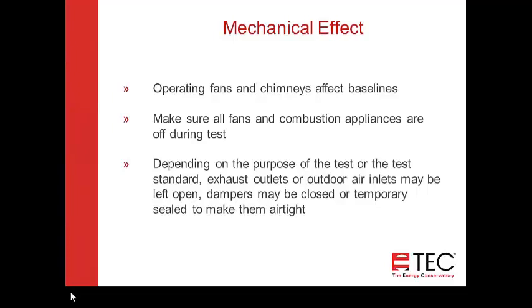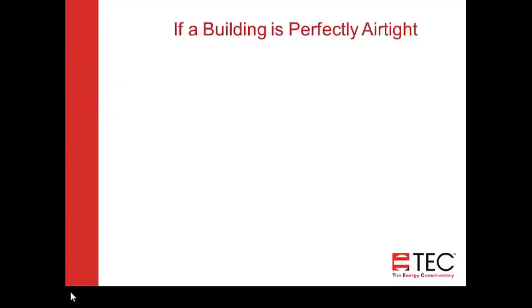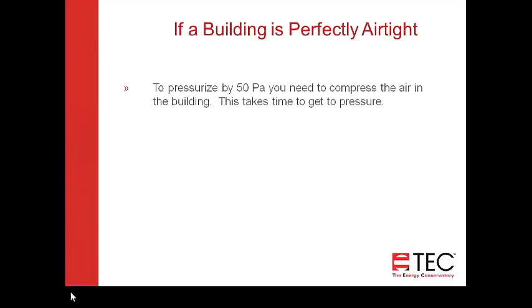Operating fans and chimneys will definitely affect your baseline and pressures in the building. You need to make sure all fans and combustion appliances are off during the test. This requires getting mechanical people out there who understand the building to make sure everything is turned off. Even when they think everything is off, you'll get on the roof and still find some exhaust package rooftop units running. One thing that's very different going from single-family residential to commercial buildings is the size of exhaust and outdoor air inlets — sometimes the size of an overhead garage door — which are intentional openings you want to make sure are sealed or temporarily sealed during testing.